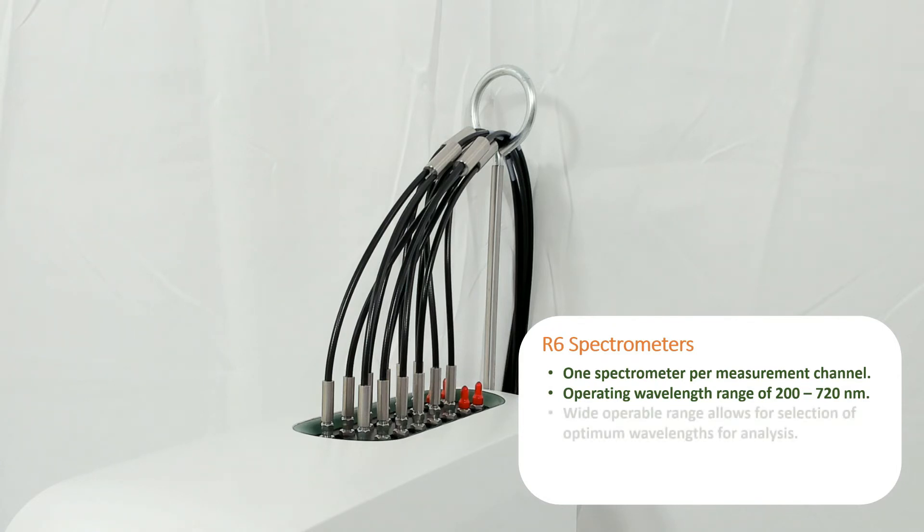In such cases, being able to assess the full UV-vis absorption spectrum of an analyte is essential. Dilution steps are not possible during in-situ analysis as they are with offline quantitative techniques, so being able to select wavelengths unaffected by peak saturation or distortion from turbidity is important for accuracy in measurements of concentration.